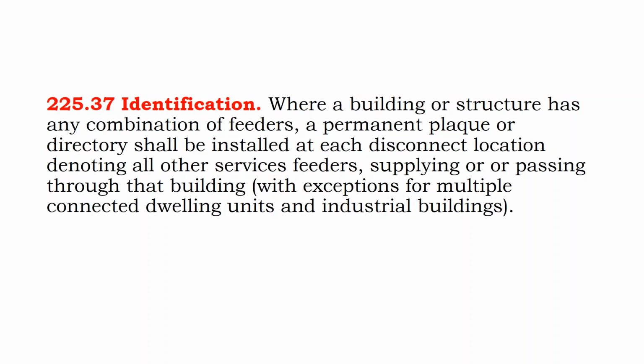Section 225.37, identification: where a building or structure has any combination of feeders, a permanent plaque should be installed at each disconnect, denoting the location of all services and feeders. And in solar, one thing that can really get you hung up on inspection is keeping track of all the labels and warnings and stickers that you need to put at each location. It's called out in section 690, so there's repetitive content. You can be flipping back and forth through 690, getting your list of stickers, and there are updates to the information on these stickers.